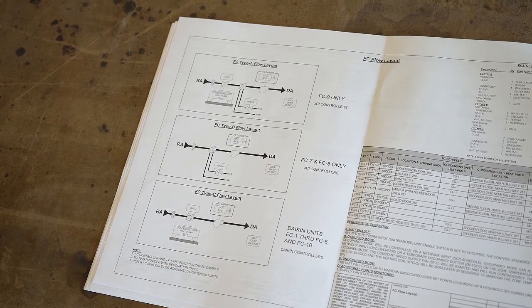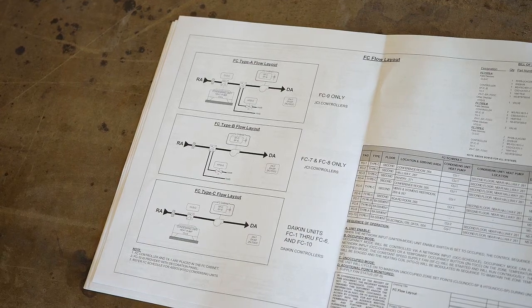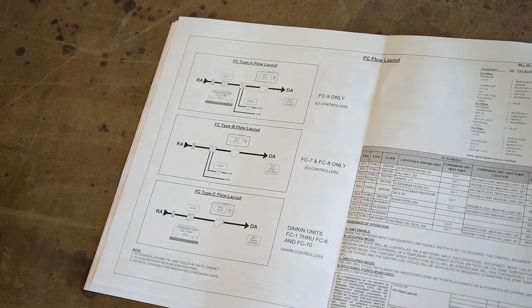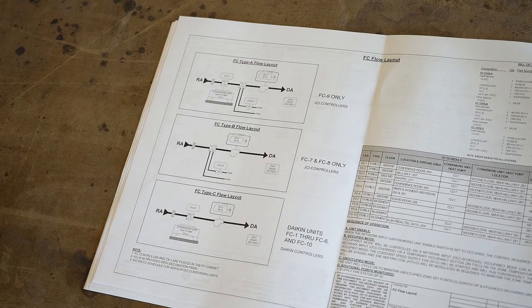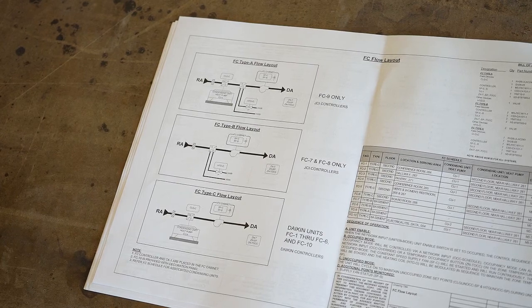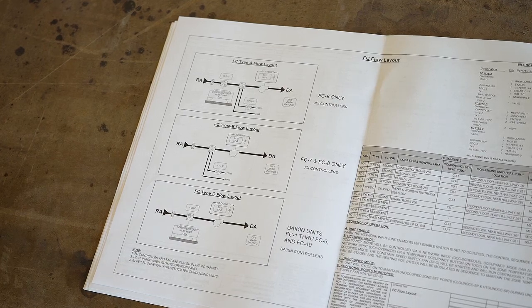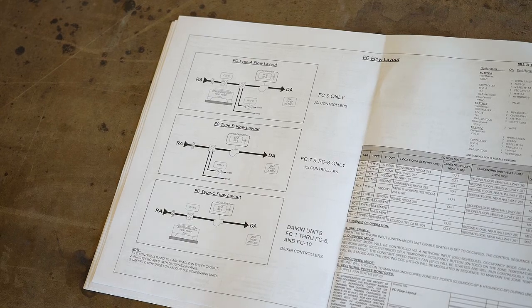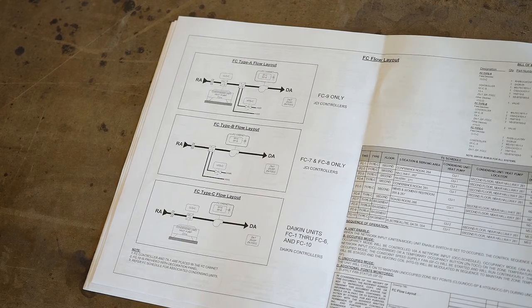They're all wired back to a valve somewhere. Well, the Daikin units go from the condensing units and they daisy chain to all the cassettes. Yeah. Then the cassettes go to each individual thermostat. Then there's a separate wire coming off of the condensing unit outside, the master, to the Daikin BACnet interface panel, which is located down in the boiler room or the heat exchanger room.